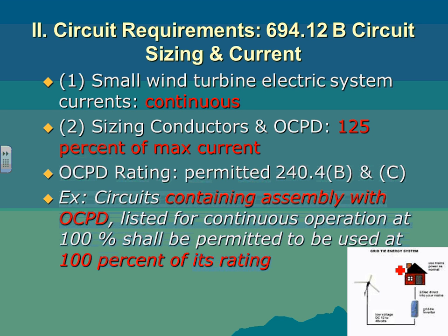I don't know how many of you guys are familiar with 100% rated circuit breakers you installed. If you dealt with anything 1000 amp or higher, you're probably familiar with something called 100% rated circuit breakers. Circuit breakers cannot, by design, produce more than 80% of their rating. So when they tell you you have 100 amp in your house, you really have 80 amps. Now, when you get typically higher than 1000 amp, they become more robust, bigger, typically power electronic trip circuit breakers, and they rate them, they don't have to, but typically they rate them for 100%, meaning when they give you a 4,000 amp power circuit breaker, it's rated for 4,000 amp. Pull the 4,000 amp out of it. Never seen a system pulling 4,000 out of it and stay running. So that's what this tells you.